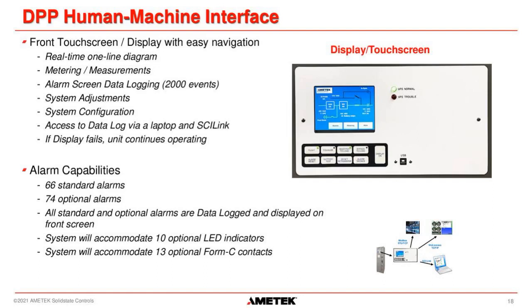And the display is completely independent of the charger and the rectifier systems. The display can completely fail, and your load will still be backed up by the UPS. We have 66 standard alarms that are in all DPP systems and an additional 74 optional alarms. All standard and optional alarms are logged when they activate, and they are displayed on the front screen. We also have the ability to accommodate up to 10 additional LED indicators on the front panel that can be mapped to certain alarms. The same goes for 13 optional Form C contacts that can be mapped to alarms specified by the user.